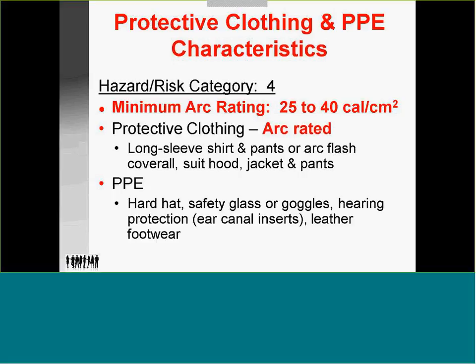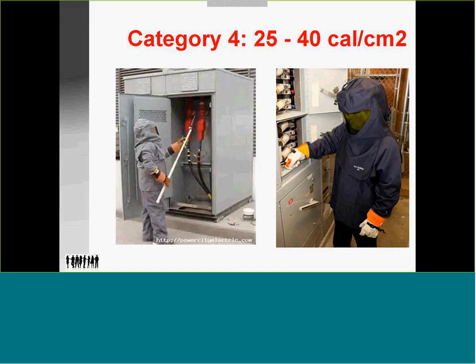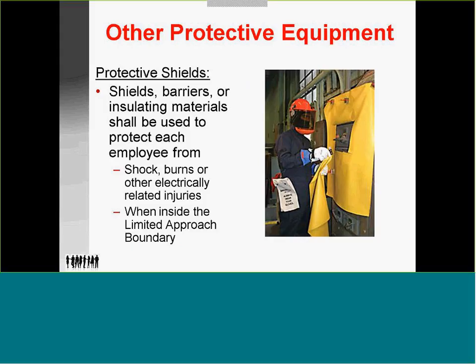Category 4 is 25 to 40 calories. Arc rating: long sleeve shirt and pants or arc coveralls, suit, hood, jacket, and pants. The reason they have lowered the lighting is they've increased the thickness of the category 4 suit. It's the same as the others. This is getting into much higher voltage. These are category 4s, what they're working on.